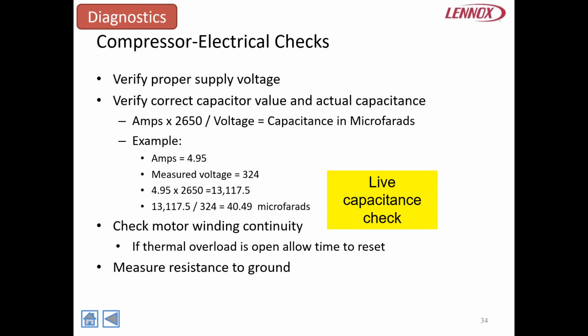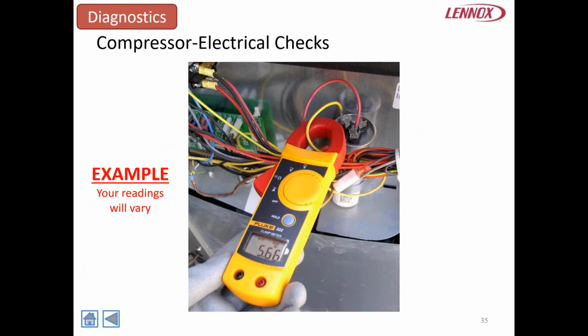Be careful. You are dealing with live voltage, but it's basically amps times 2650 divided by the voltage, and that gives you the capacitance of what that capacitor is actually rated at, or what it's reading at that point in time. So let's walk through an example with an actual unit running. With the unit operating at full capacity, we want to check the HERM off the run capacitor. In this example, we're going to get 5.66 amps AC.